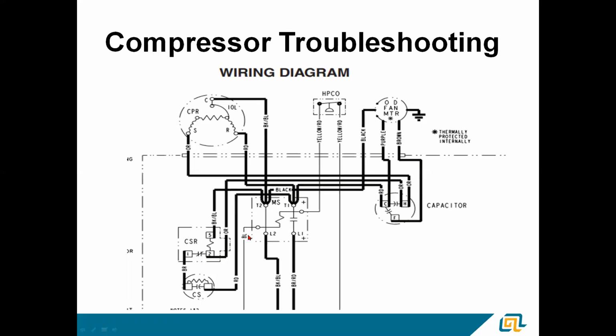So here's a contactor. MS on our drawings is a motor starter or a contactor. If you notice, they're clearly showing us a contact between L1 and T1. Over here on L2 to T2, that's just a bar, a shunt they refer to it as. So that's a constant connection. That connection never goes away.